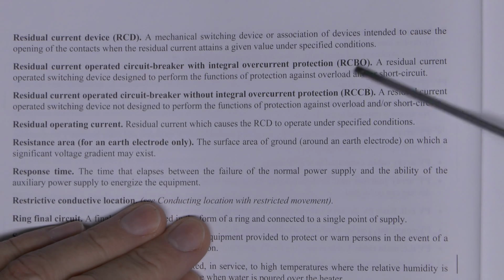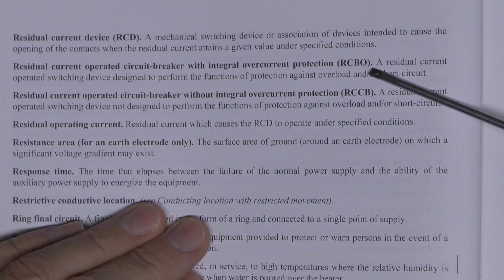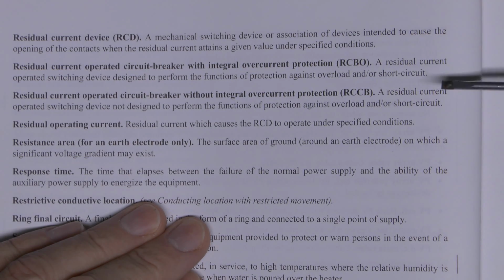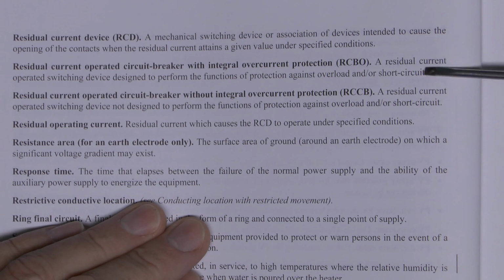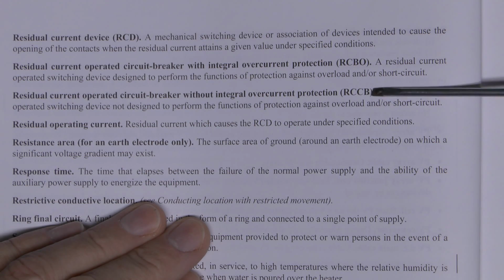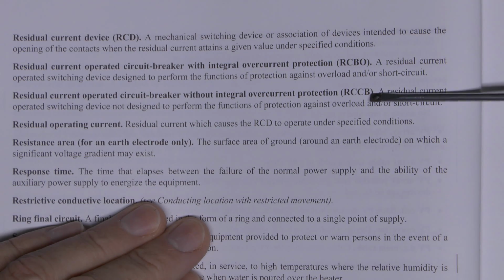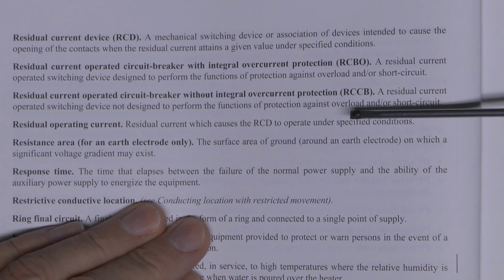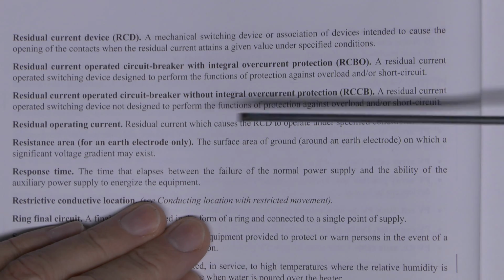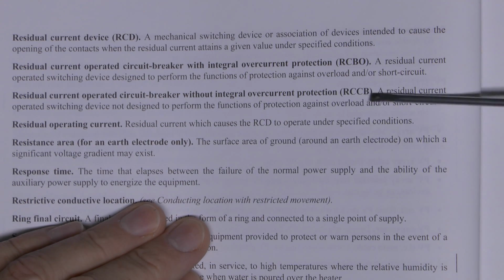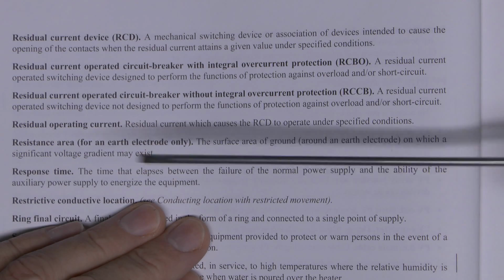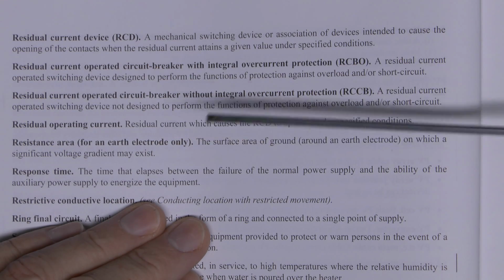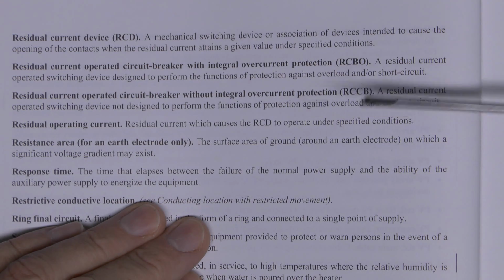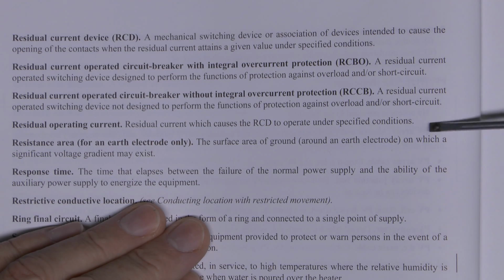The RCBO here is the one with the built-in circuit breaker, so again, as it states here, it will work on both the residual current and when there's an overload or a short circuit. And RCCB, or residual current operated circuit breaker without integral overcurrent protection, is basically the same as the RCD, it's just a different name for the same device. And the residual operating current is the residual current which causes the RCD to operate under specified conditions.